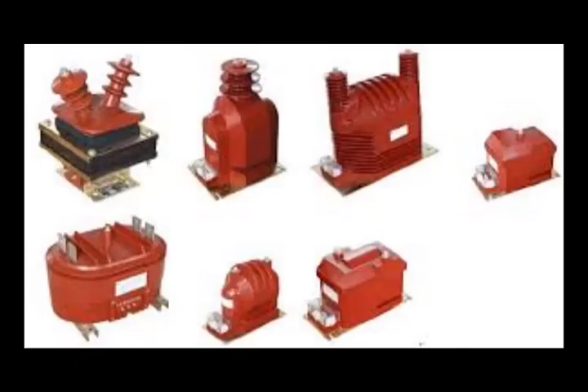The switchgear has to perform the function of carrying, making and breaking the normal load current like a switch, and it has to perform the function of clearing the fault in the power system. In addition to that, it also has the provision of metering and regulating the various parameters of electrical power systems. Thus, the switchgear includes circuit breaker, current transformers, voltage transformers, protection relays, measuring instruments, electrical switches, electrical fuses and miniature circuit breaker, lightning arresters or surge arresters, electrical isolators and other associated pieces of equipment.